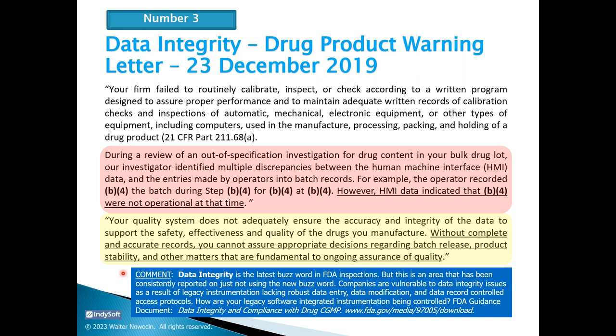Now the buzzword data integrity is the latest one used by the FDA, and you kind of get the impression that it's a new buzz, a new expectation of the FDA. It is not. In my 17 years of reviewing FDA warning letters, this is an area that has consistently been reported on, just not using the new buzzword. They used other words. So it's not necessarily new to us in the industry, but it is an FDA focus of attention whenever there's human data collection with instruments purported to be automated with embedded software.